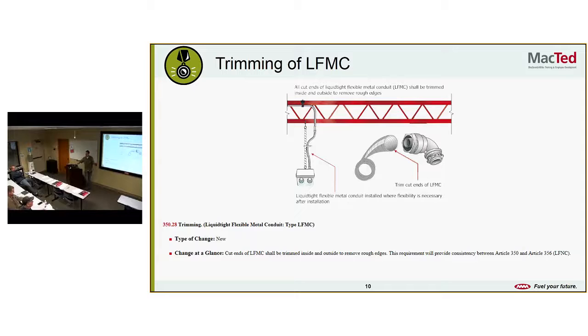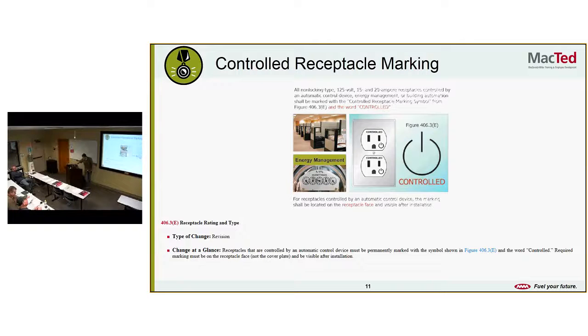Anything else? Okay. Controlled receptacle marking. All non-locking type 125 volt, 15 and 20 amp receptacles controlled by an automatic control device shall be marked with the controlled receptacle marking symbol. So it's got its own symbol now for controlled receptacle. This is a revision. Receptacles that are controlled by an automatic control device must be permanently marked with the symbol shown in figure 406.3, and the word controlled. Required marking must be on the receptacle face, not the cover plate. Oh. Yeah. So that's new.